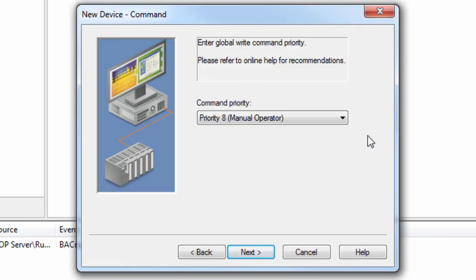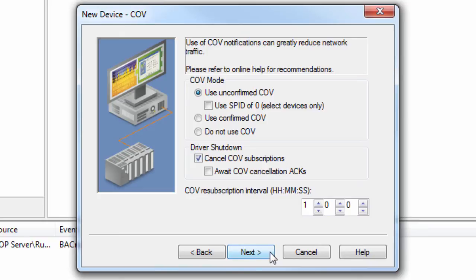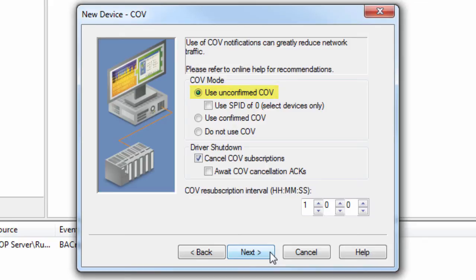Click Next to set the change of value settings. When COV notifications are used, the BACnet IP driver does not have to continuously poll the device for the current value of these properties. This reduces network traffic and the communications processing load. Use unconfirmed COV specifies that the driver will receive COV notifications from the device. The device will not expect acknowledgement of those notifications.